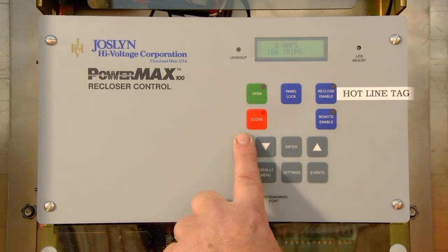Pressing this button with the recloser open will cause the control to close the recloser. When the recloser is closed, the red LED will be illuminated. Lockout conditions will be reset when this button is pressed.